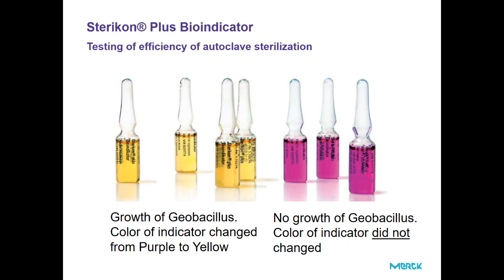The second tool is the so-called Sterikon Plus bioindicator, dedicated to testing the efficiency of autoclave sterilization. There are glass ampoules containing the spores of Geobacillus stearothermophilus, plus the growth media, plus the color indicator. So, after autoclaving, which is followed by incubation of the Sterikon ampoules, if there is no growth of the Geobacillus, it means the sterilization in the autoclave was efficient enough. There is also no change of the color, and the ampoules remain violet. If we see the color change from violet to yellow, it means that the spores of Geobacillus stearothermophilus are able to grow and change the color. It means the efficiency of autoclaving was not sufficient.